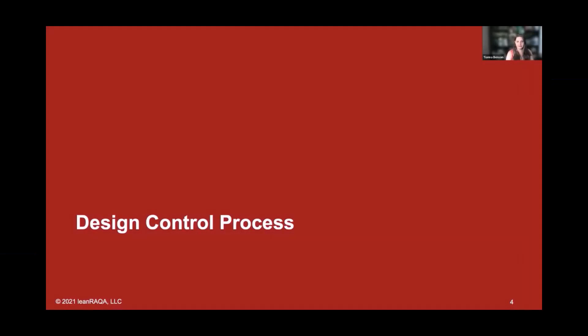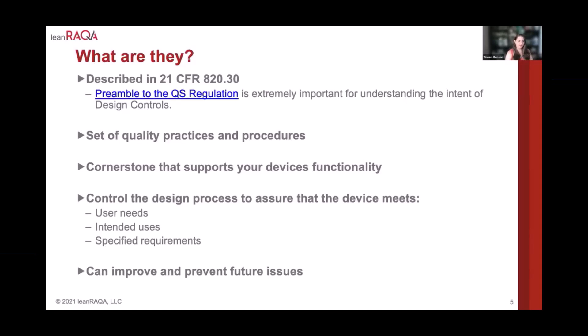Let's talk a little bit about design controls. It's something that we all hear being in the medical device industry and it's really kind of a 'what are they' moment. Design controls is really a set of practices and procedures that you follow to document your design and to show that you are building your design in an iterative and controlled fashion.